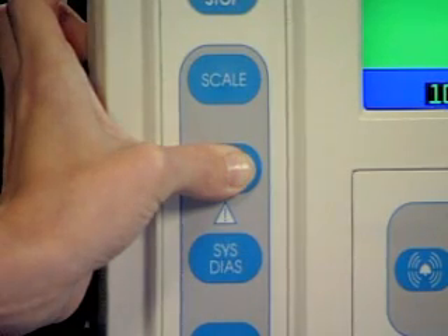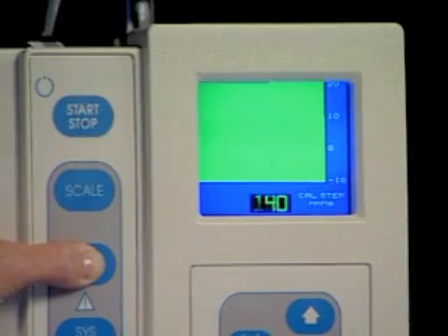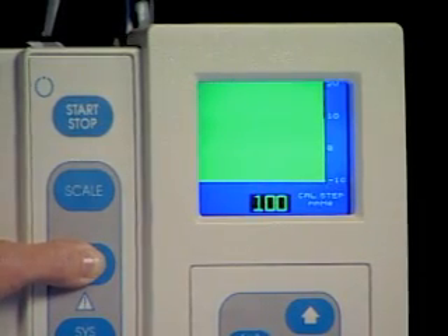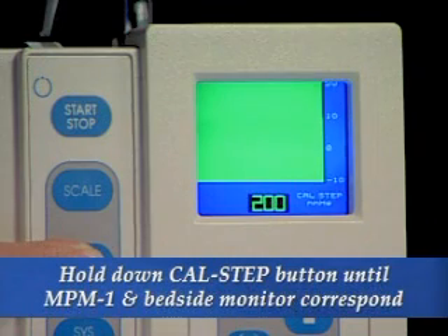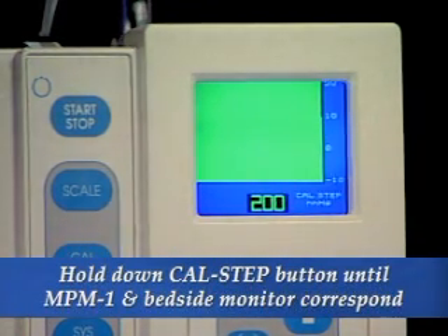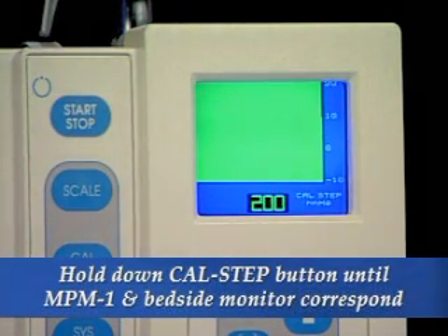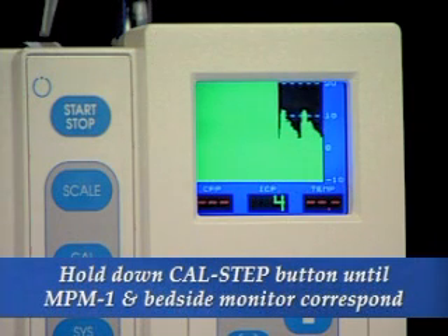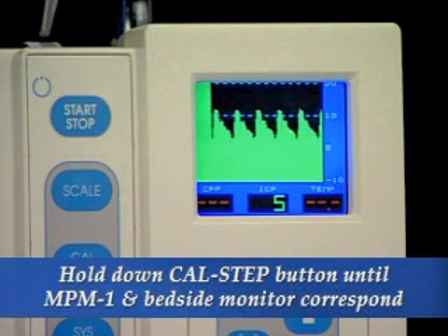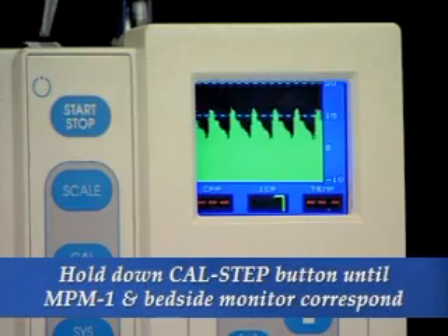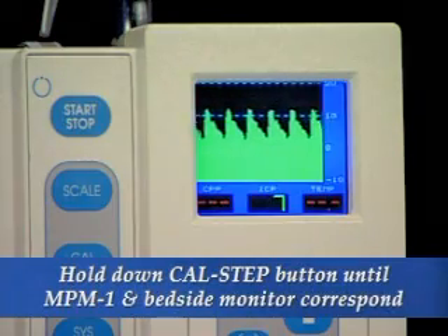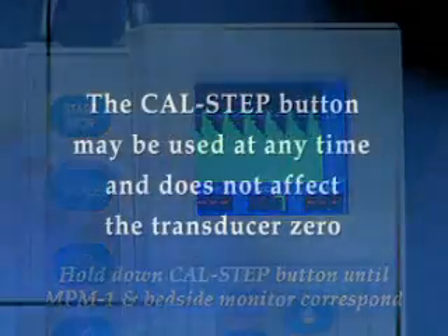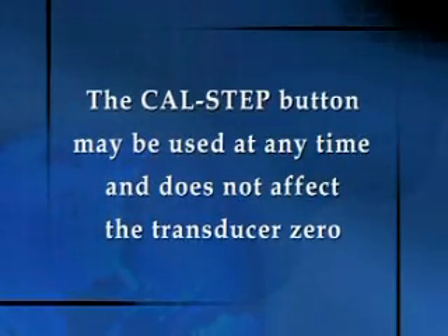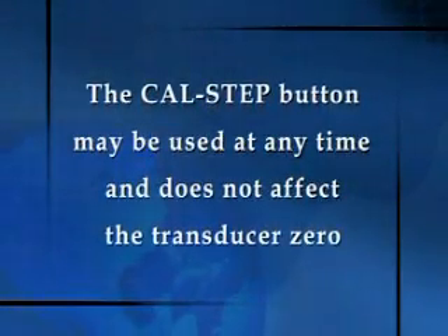Repeat this process through the calibration step increments of 40, 100, and 200. It is important that you hold down the CalStep button until the values on the MPM-1 and bedside monitor correspond. If not held, the MPM-1 display will revert to normal pressure monitoring before the synchronization is completed. Note that the CalStep button may be used at any time and does not affect the transducer 0.